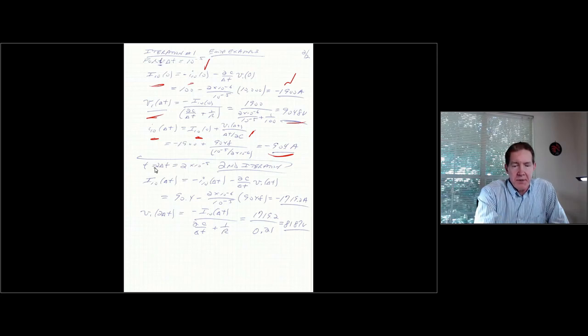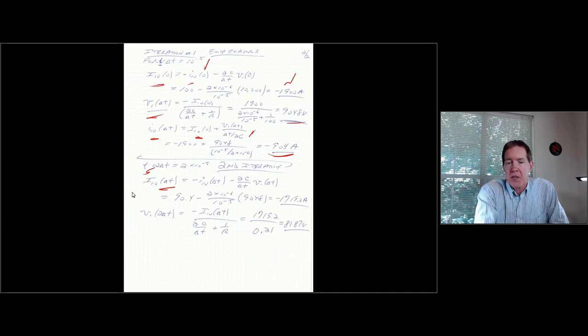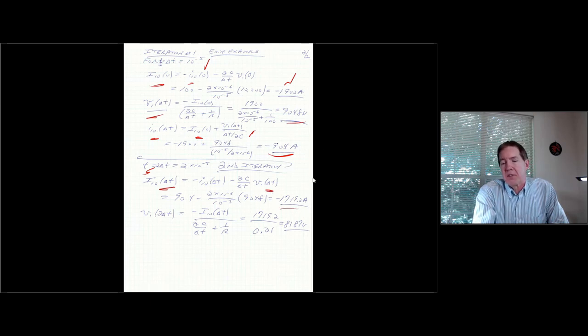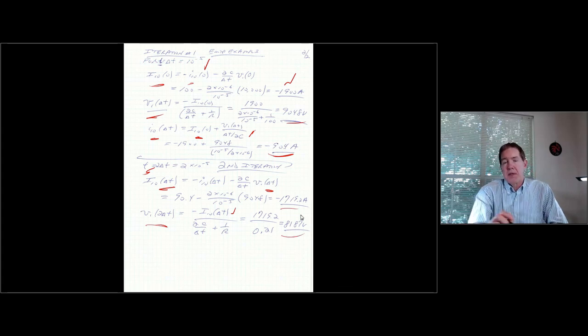For the next iteration at time T equal to 2 delta T, we just go through the same process again. So now what we want, we calculate the history. This time it's at time delta T. This is going to be minus I10 at delta T, which is the branch current, the minus value of the branch current at time delta T. Minus 2C over delta T times V1 at time delta T. This is going to give us minus 1,719.2 amps. And then I plug this back into the equation for voltage. And this is going to give us a voltage of 8,187 volts.